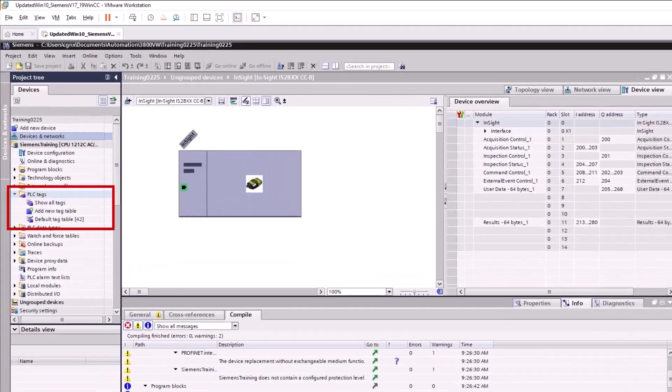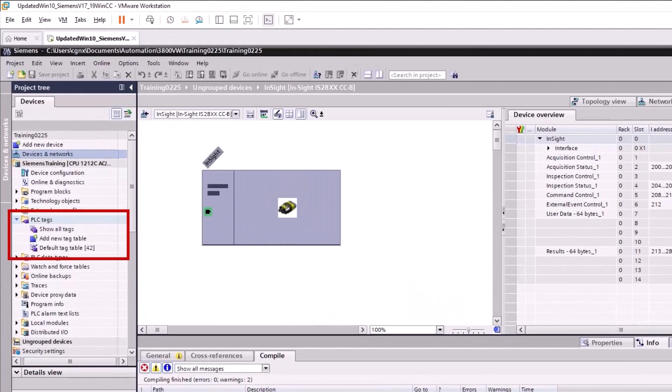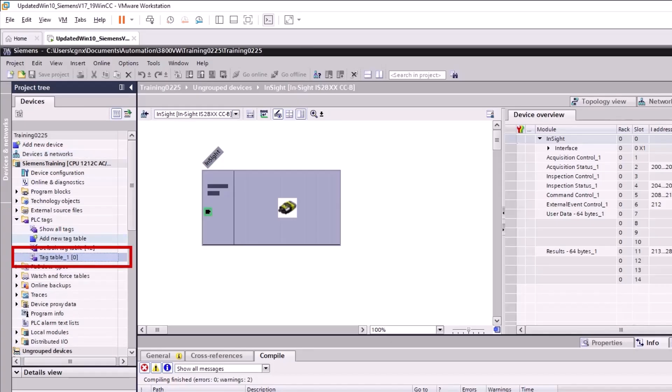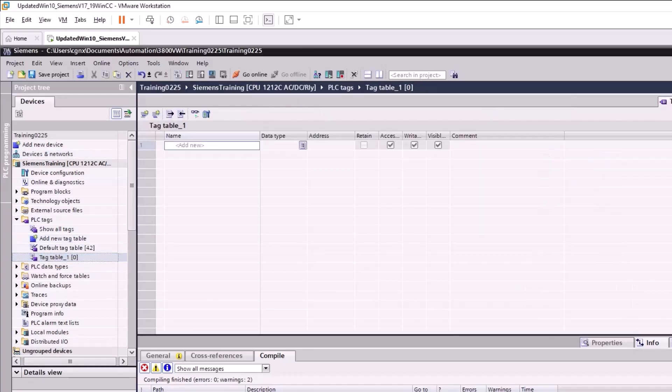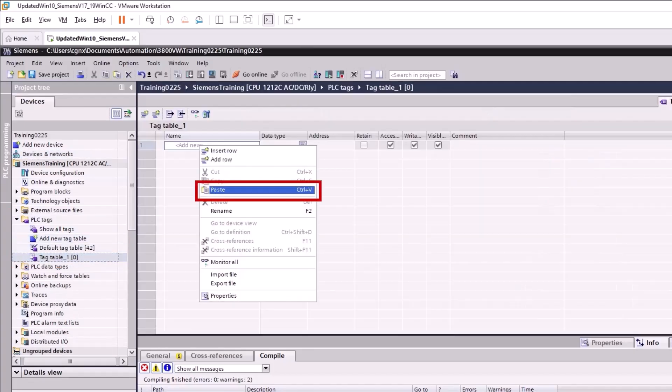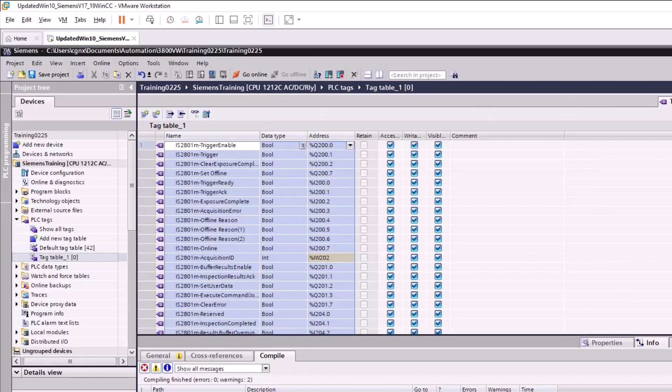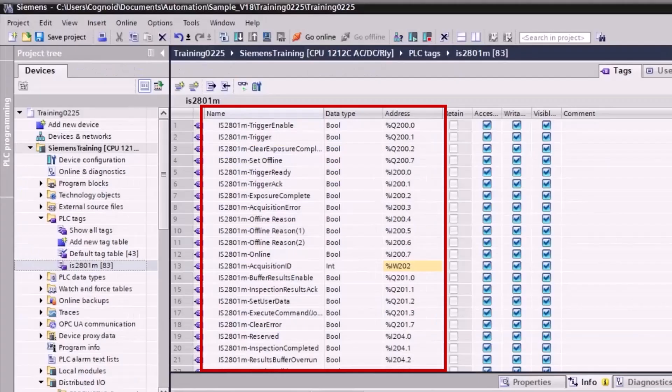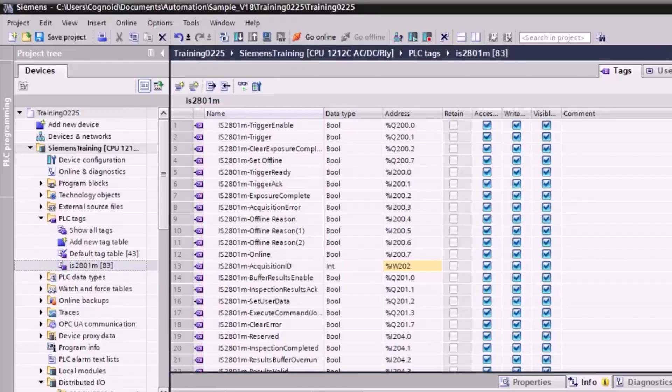Under the PLC Tags heading in the Device pane, select Add New Tag Table. Right-click in the first open Tag Name space and paste the contents from the Excel spreadsheet. The Tag Names, Data Types, and Addresses are now populated and all tags have been generated. These tags can now be used throughout the PLC logic.